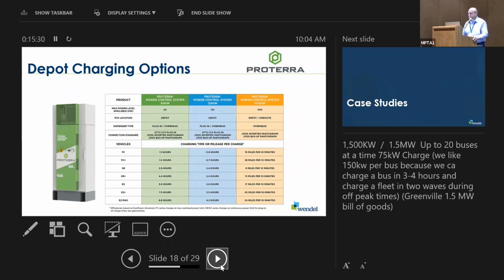So essentially, you really need to look at all the different considerations of how you want to charge your fleet. For example, Proterra has a 1.5 megawatt charging system—you drop it down, put 20 charging heads out, and charge 20 buses at 75 kilowatts at a time. If you're filling that battery pack, you're looking at 6 to 7 hours. And as you get to these 500-600 kilowatt hour battery packs, now you're talking 7 to 8 hours.